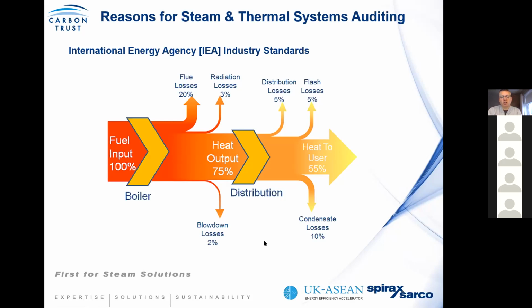When we consider a study conducted by the International Energy Agency, they have determined that in general only about 55% of the fuel energy that goes into a steam system is used effectively by the process itself. So in other words, a very inefficient system. They have identified what actually happens and what contributes towards those losses. Throughout the next few slides, we're going to give you some insight on how to counteract these losses to improve the efficiency of your total steam system. Please remember this introduction slide, because once we come to the conclusion of this session, we'll revert back to the slide and give you some insight as to how to further optimize your system.